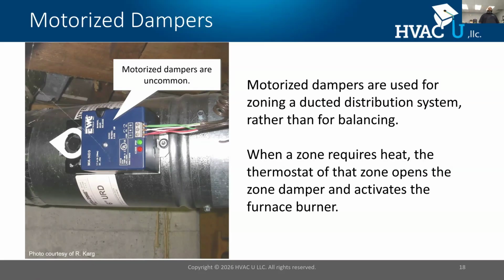So what we do with a motorized system, we're going to put dampers in all the branches and we're going to separate them. Oftentimes what we do, we put the duct runs that are going on the second floor on a zone, and the duct runs going on the first floor on a zone. And then we use 2 thermostats and we offset those. And when we offset them and the ductwork is sized appropriately, we can deliver conditioned air just to the zone it's calling. When done effectively, studies have shown that this has been able to save about 10% of energy savings. All right, that's motorized dampers.